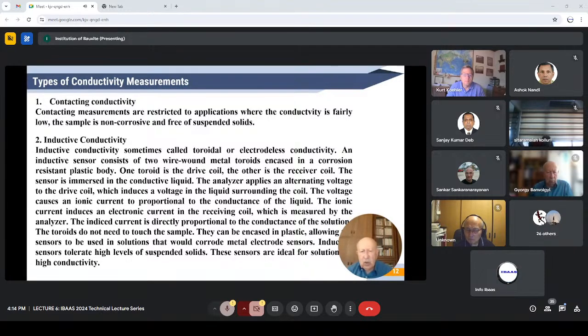An inductive sensor consists of two wire-wound metal toroids encased in a corrosion-resistant plastic body. One toroid is the drive coil, the other is the receiver coil. The sensor is immersed in the conductive liquid. The analyzer applies an alternating voltage to the drive coil, which induces a voltage in the liquid surrounding the coil. The voltage causes an ionic current proportional to the conductance of the liquid. The ionic current induces an electronic current in the receiving coil, which is measured by the analyzer. The induced current is directly proportional to the conductance of the solution.